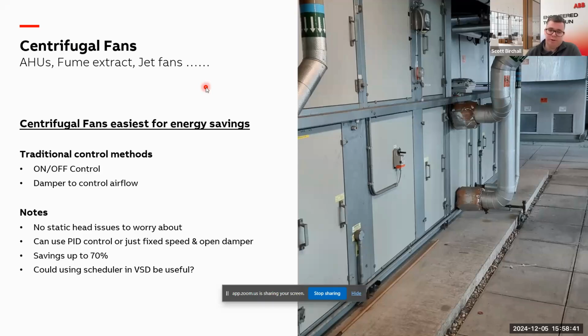A lot of traditional control methods, like on-off control, aren't actually speed controlled at all, and they might be mechanically restricted by a damper or some kind of flow restriction. So they're easy to save with, up to 70% we've seen. You can use schedulers in a VSD if you need to install it after the fact. This is a picture of a typical air handling unit, for example.